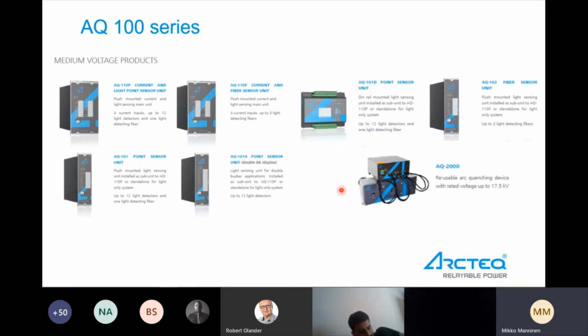For the medium voltage, we have AQ2000, which is a reusable arc quenching device, rated voltage up to 17.5 kilovolts. And it can be tested. Mechanical lifetime or mechanical testing cycles can be up to 20, and actual quenching in a real situation up to 2 times.